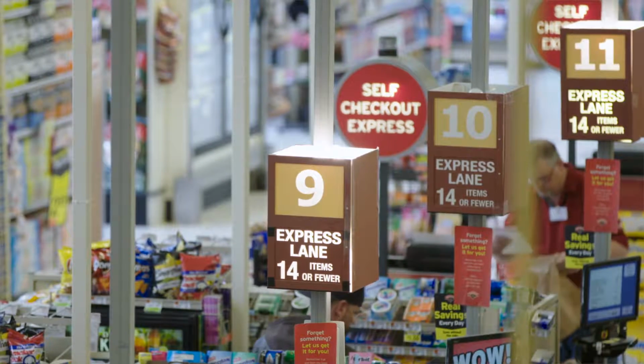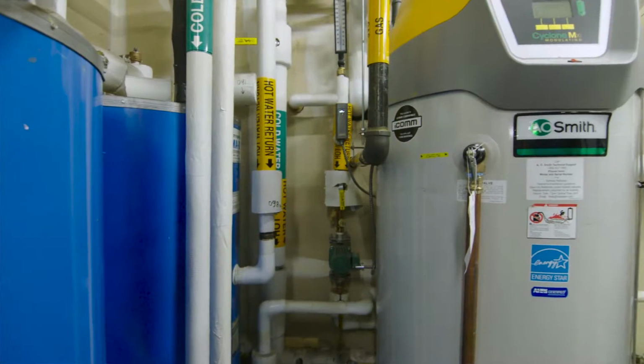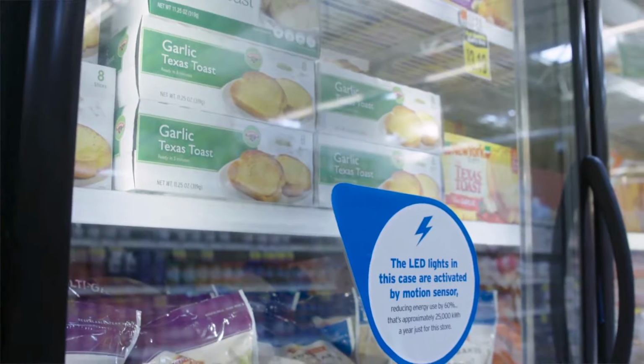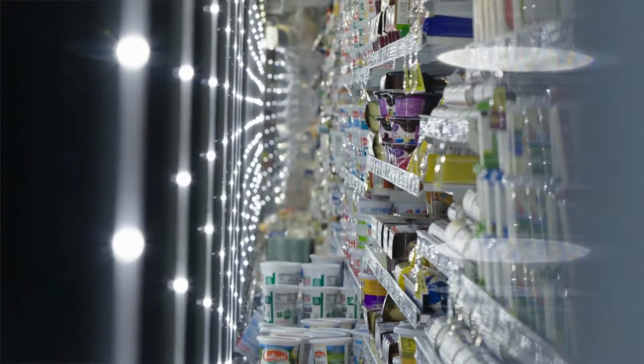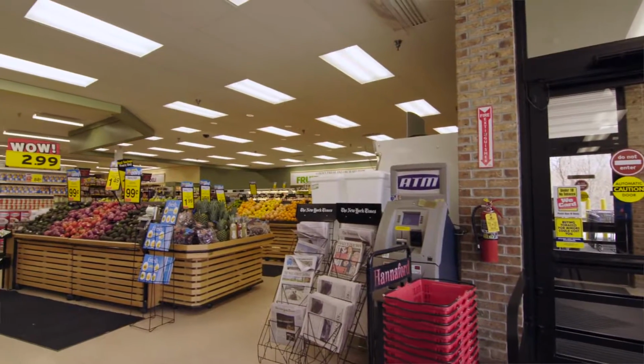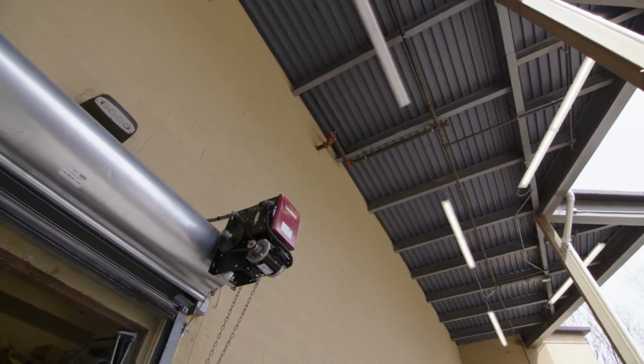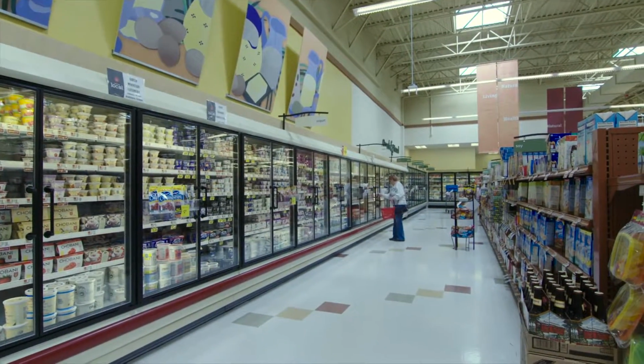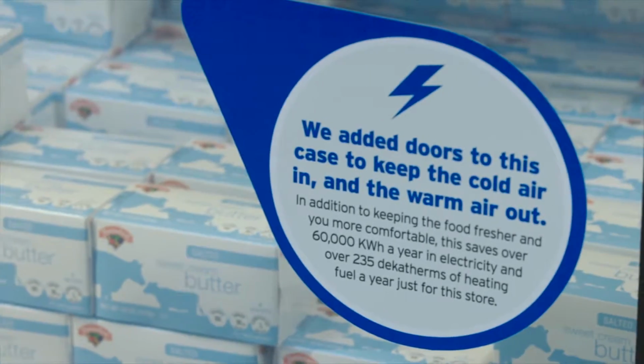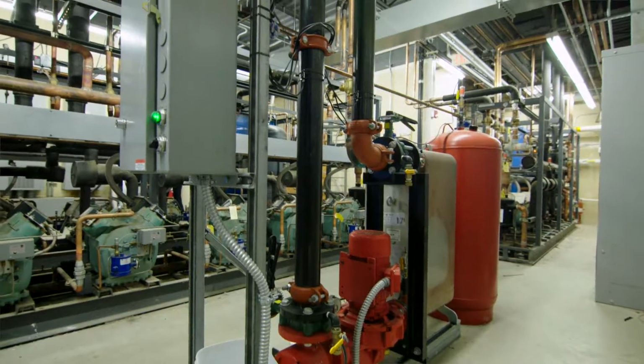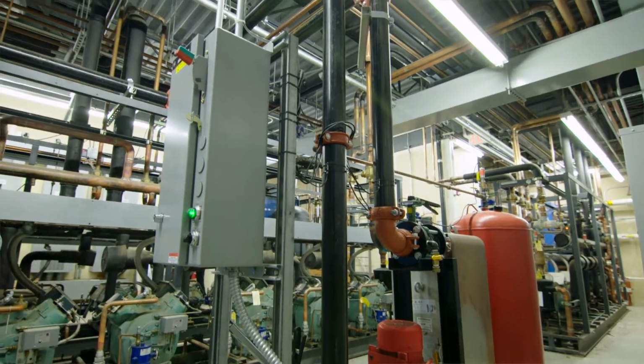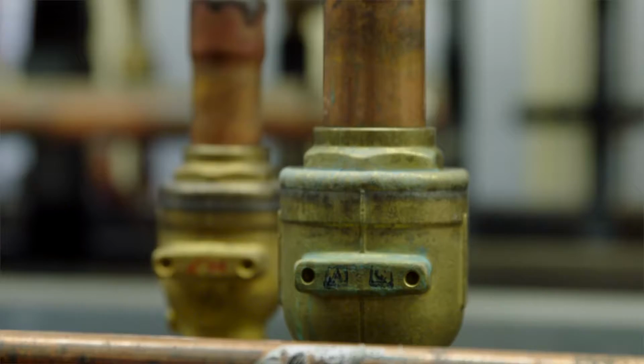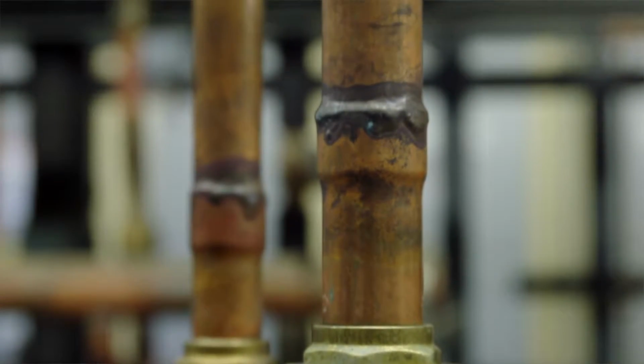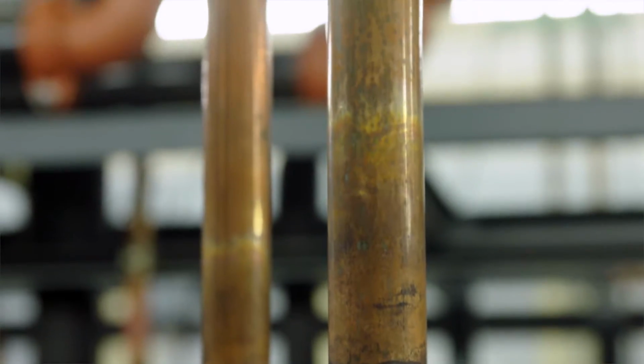We can advocate for more energy efficient equipment in the new stores and in the remodels, bringing them down to a 4-year ROI or less. Some of the projects we've been doing in Vermont include replacing our case lights to LEDs. We'll also do main aisle lighting and peripheral lighting upgrades to LED as well, with motion sensors. We've been putting zero energy glass doors on the refrigerated cases to contain all the cold air. We connect a glycol heat exchanger to our refrigeration rack. We're actually extracting the heat from there, transferring it to a glycol that goes into our rooftop air handlers, and using that to reheat the store.